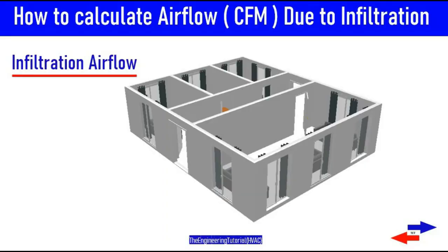The topic of this video is going to be airflow calculation due to infiltration. As you might know, in a typical building, air leaks into or out of a space through doors, windows, and small cracks in the building envelope. So air leaking into a space is called infiltration.